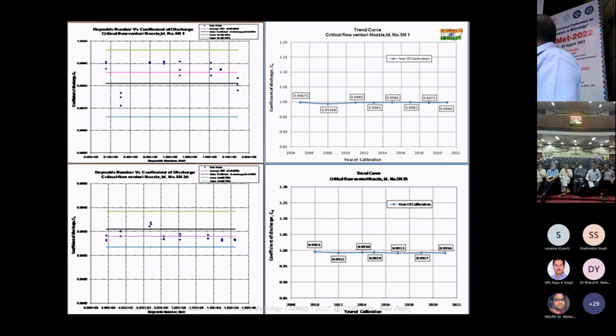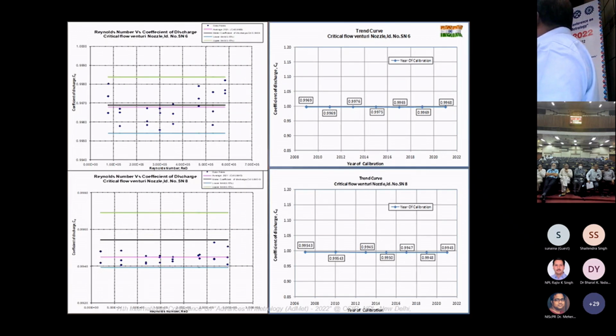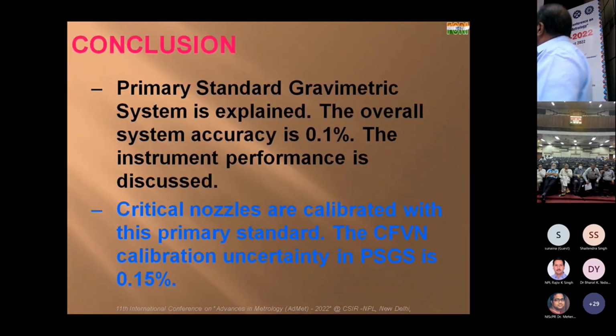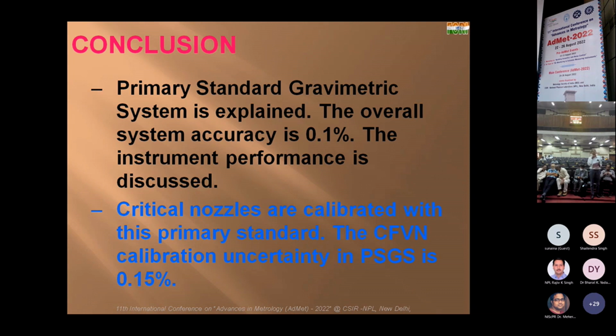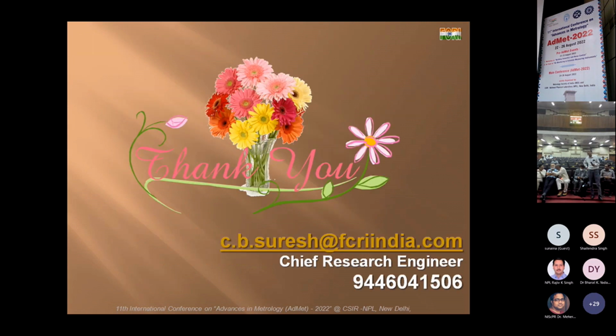These are also some of the results when we calibrate critical nozzles. Each nozzle is calibrated at the center, and you can see 12 years of history of the different nozzles. Overall system accuracy is only 0.1% in the gravimetric system, and with calibration of the critical nozzle we land at around 0.15%. Of course, we also calibrate turbine meters and PD meters, but their accuracy is slightly lower. So briefly, I have explained the gravimetric system. Any questions?